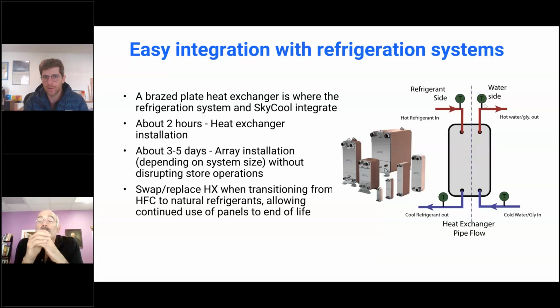But there is more of a decision tree than like a set of sophisticated logic, that's how I would describe it. But for example, we don't want the refrigerant to get too cold, so we'll slow the pump down if it starts to get too cold in the winter. We can direct flow from a subcooling heat exchanger to a pre-cooling heat exchanger, and there's a 3-way valve in the system, so that will direct the flow then.